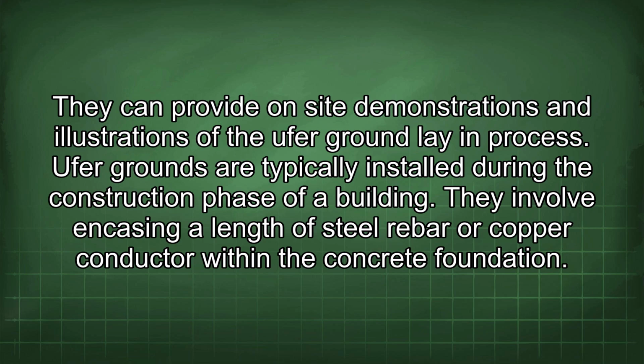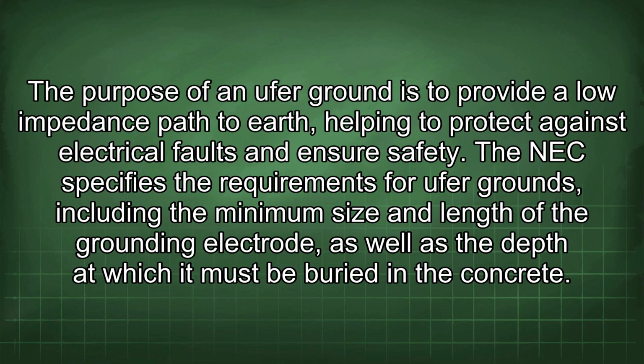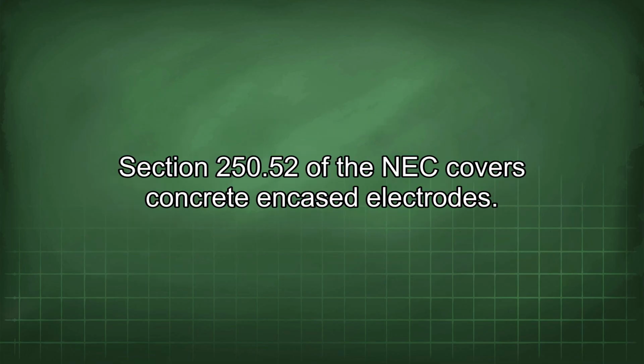Ufer grounds are typically installed during the construction phase of a building. They involve encasing a length of steel rebar or copper conductor within the concrete foundation. The purpose of a Ufer ground is to provide a low-impedance path to earth, helping to protect against electrical faults and ensure safety. The NEC specifies the requirements for Ufer grounds, including the minimum size and length of the grounding electrode, as well as the depth at which it must be buried in the concrete. Section 250.52 of the NEC covers concrete encased electrodes.